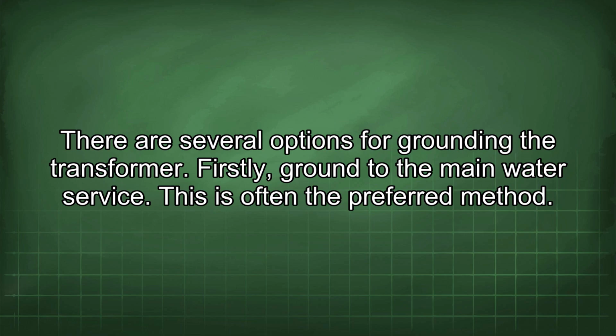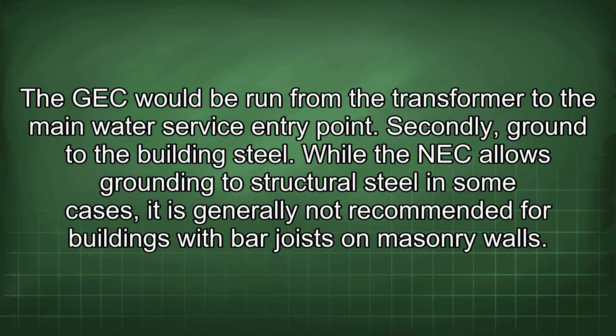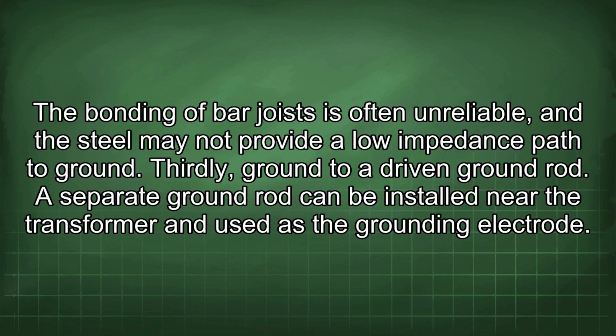Firstly, ground to the main water service. This is often the preferred method. The GEC would be run from the transformer to the main water service entry point. Secondly, ground to the building steel. While the NEC allows grounding to structural steel in some cases, it is generally not recommended for buildings with bar joists on masonry walls.